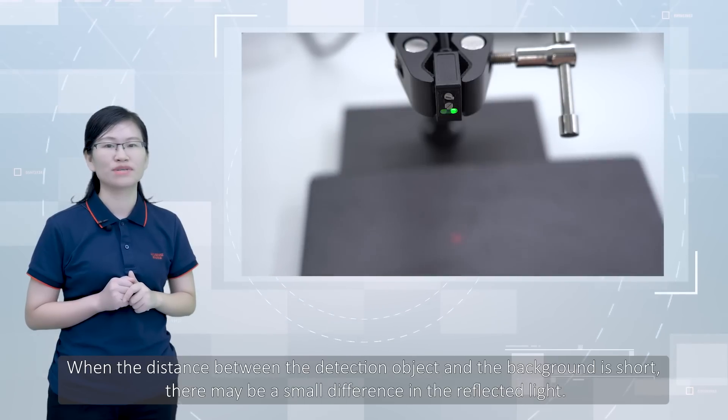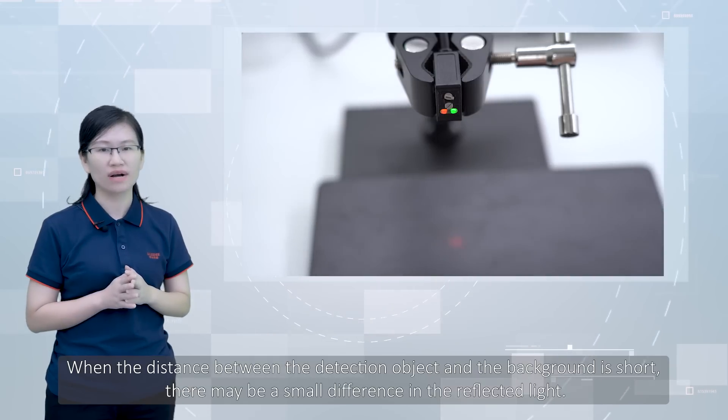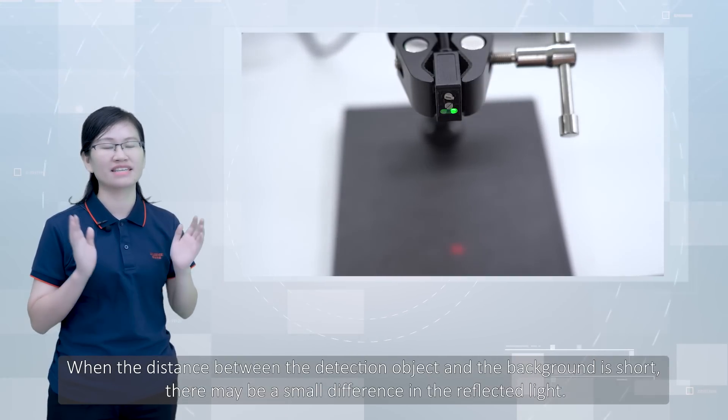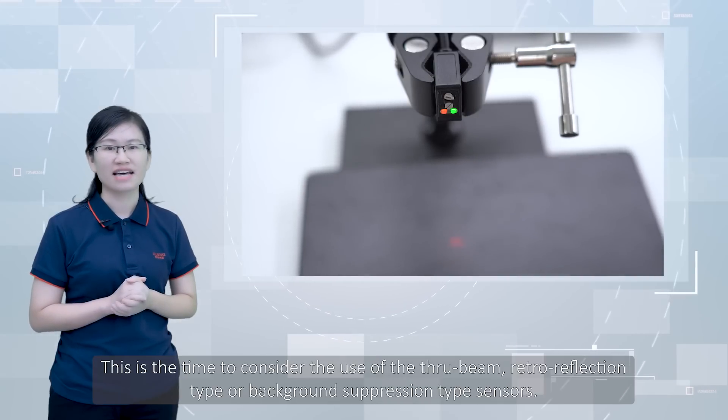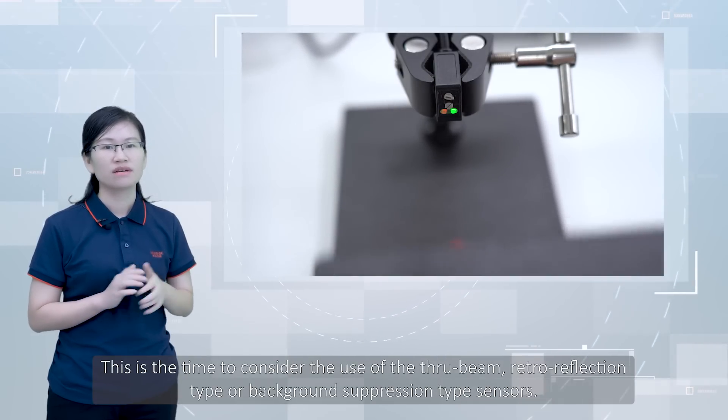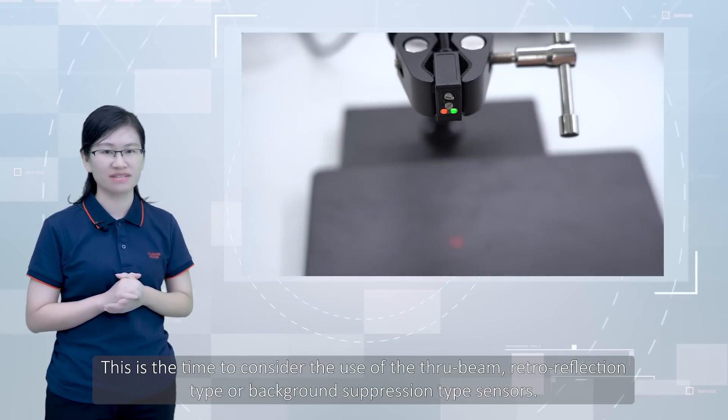When the distance between the detection object and the background is short, there may be a small difference in reflected light. This is time to consider the use of the through-beam, retro reflection type, or background suppression type sensors.